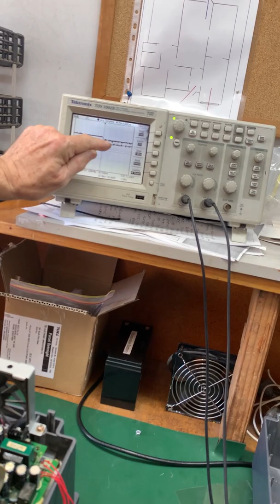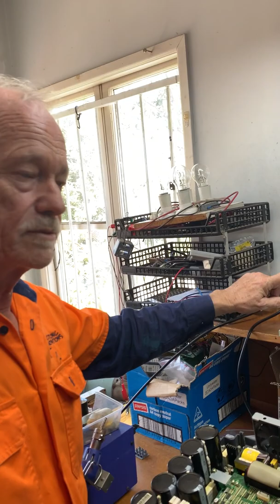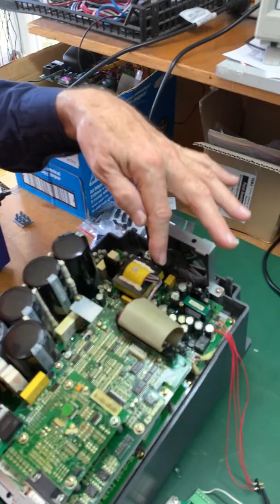This bottom one is the 5-volt supply, and we see that, it starts to go up. This is in the circuitry that goes to the opto-isolator, and the opto-isolator is telling it, is the voltage too high or is it too low? And here, abruptly, it says that it's too low, and naturally the circuit increases the voltage. So that is the fault, and it must be somewhere in the circuitry here.